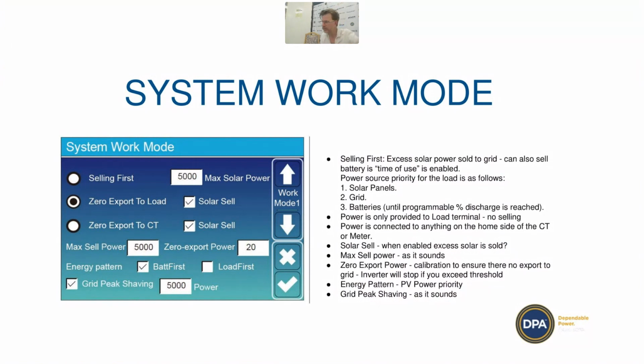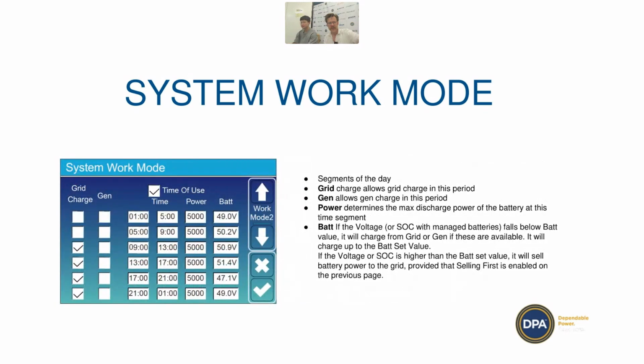And then we've got energy pattern, and that's just the PV power priority, whether it's going to go to the battery first or to the load. And then peak shaving is if you want to limit the amount of power that you're going to pull from the grid. So we've selected zero export to load, zero export to CT, one of those two, for instance. And then we're going to go on to this next page, which is time of use.